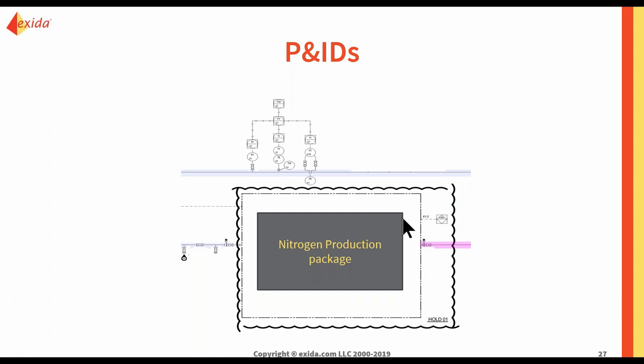So in the end, because we do not know the piping, the valves, and everything, we could not do a HAZOP. Because when we do a HAZOP, we have to look at the point of failures. We have to look at specifically what valve might fail, what section of piping might fail in a way that is going to propel and cause that particular hazard. In a situation like this, with a blank package, we can at most only do a what-if. So we did about a week of what-if, but after 2 or 3 months, after we received all the information about these packages, we went back and did about 2 or 3 weeks of HAZOP on that.